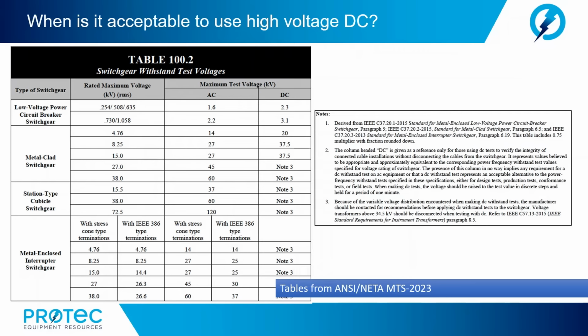All right, and now we'll take a look at Table 100.2, switchgear withstand test voltages. Again, we do see that our main callout is AC voltage, but we do see a column at the end of the table for DC. But again, we need to refer to the notes. The column headed DC is given as a reference only for those using DC tests to verify the integrity of connected cable installations without disconnecting the cable from the switchgear.